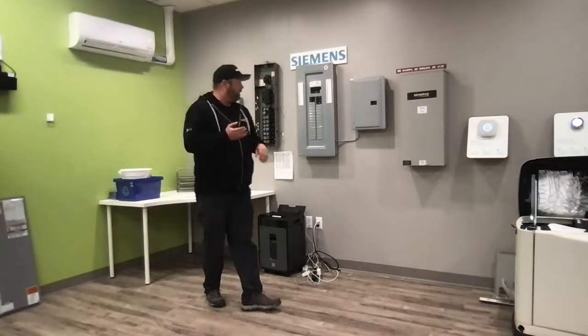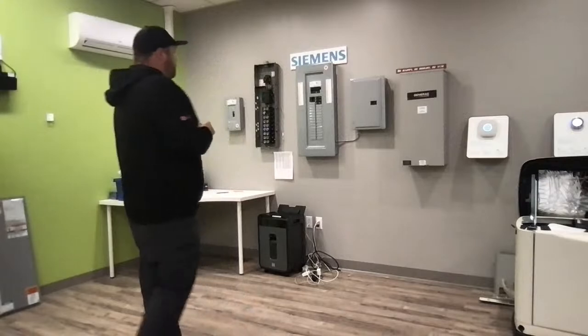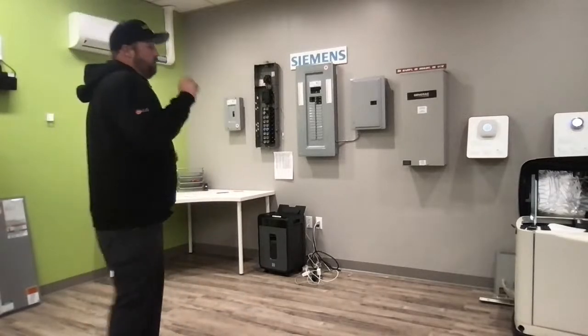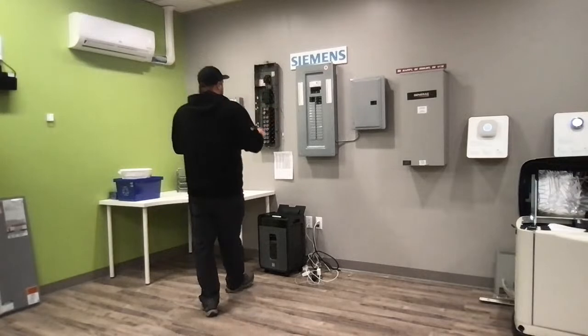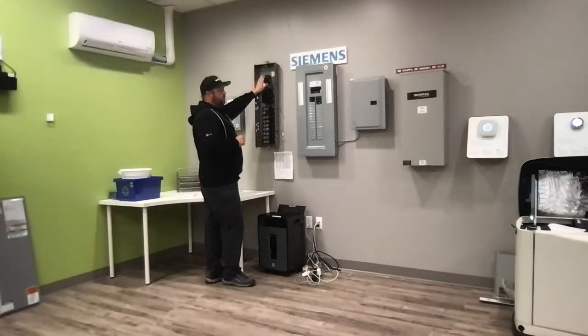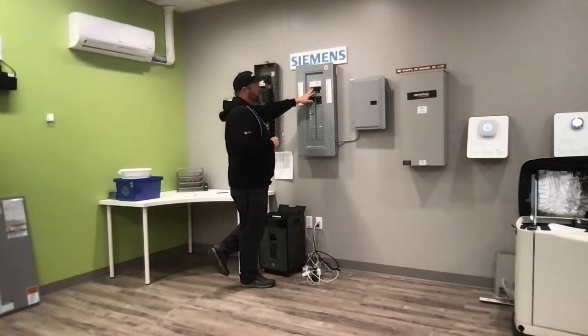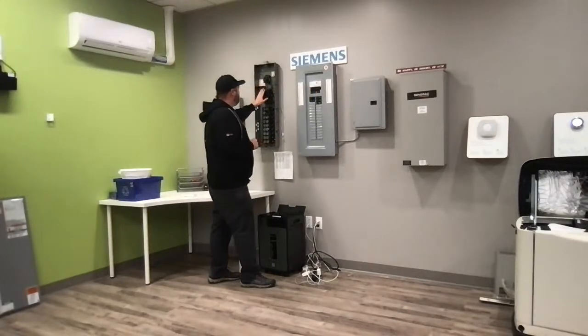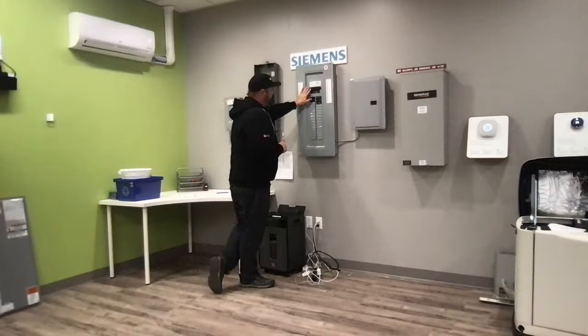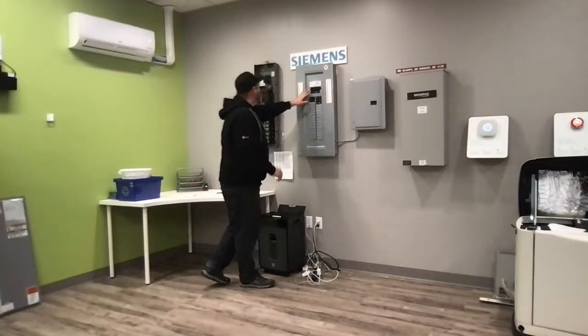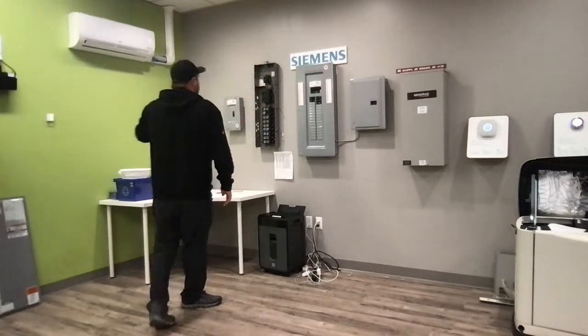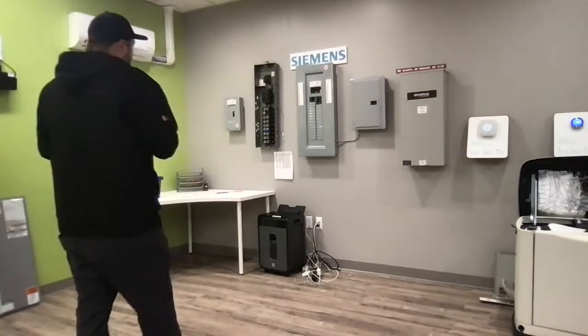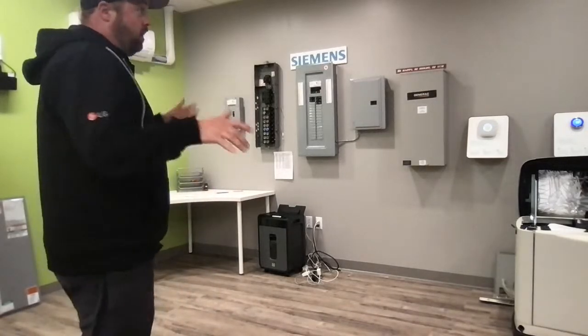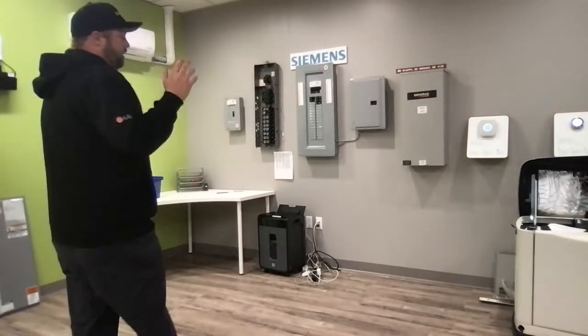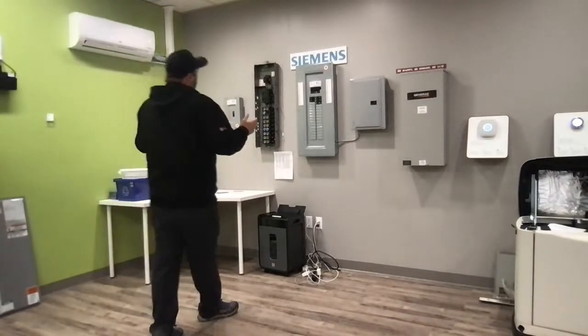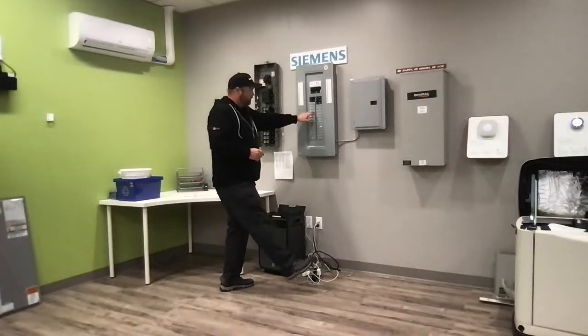If you heat with oil and you're going to keep oil, you can fit in a few heat pumps, you still have enough power. What you can't do is come off of oil on 100 amps. This is a 100 amp panel, this is a 200 amp panel. If you want to come off of oil, 99.9% of the time you're coming over to a 200 amp service. The reason is we can get the heat pumps in, but if you remove the oil, you have to replace your primary heat source, and 99% of the time we do that with electric. That electric is going to make you have to jump to that 200 amp service upgrade.